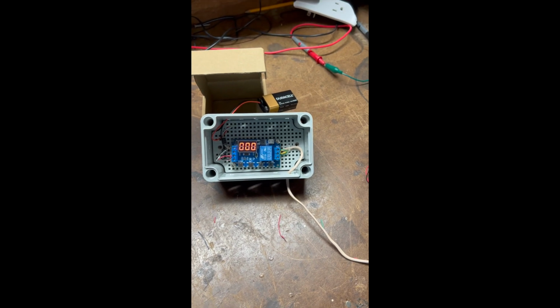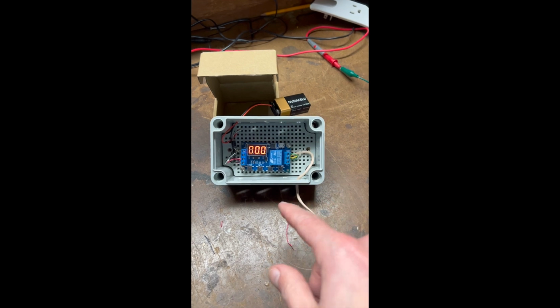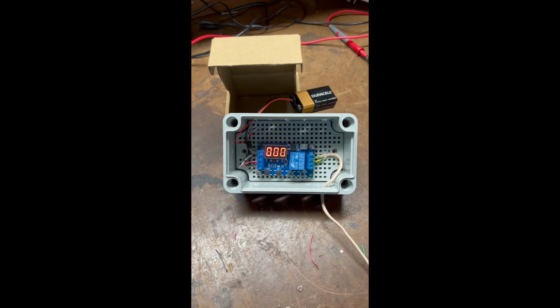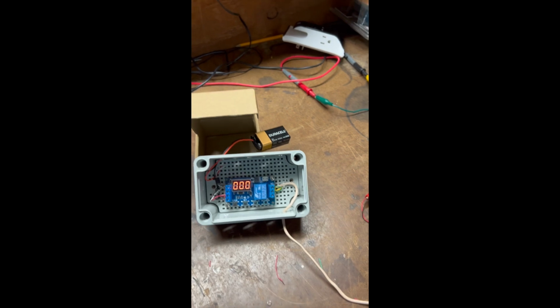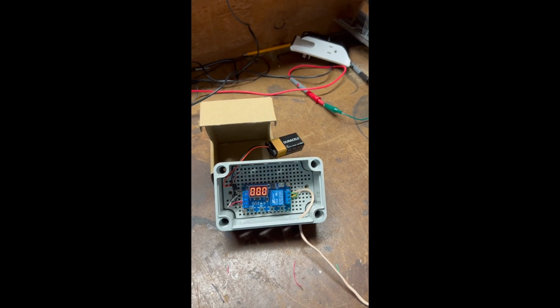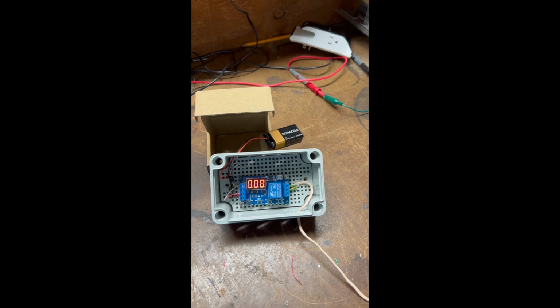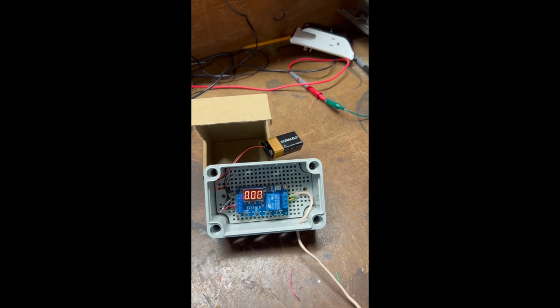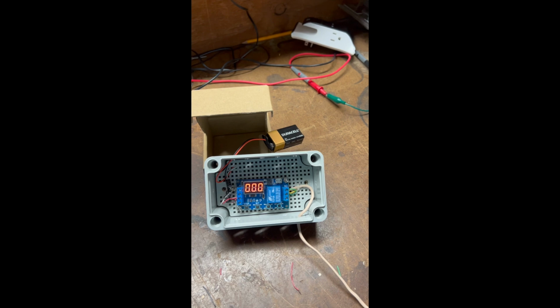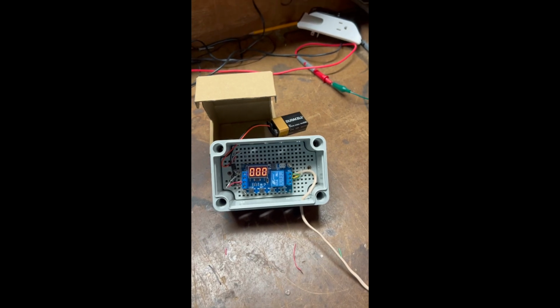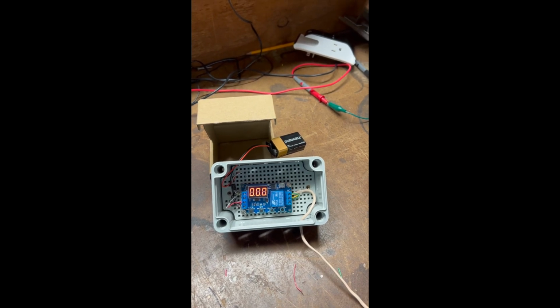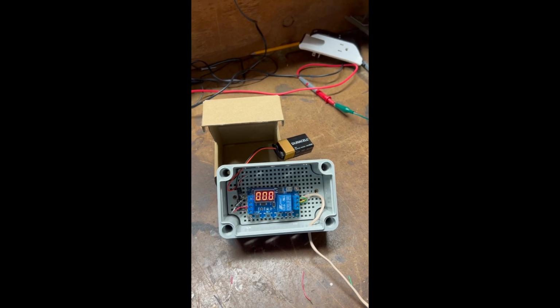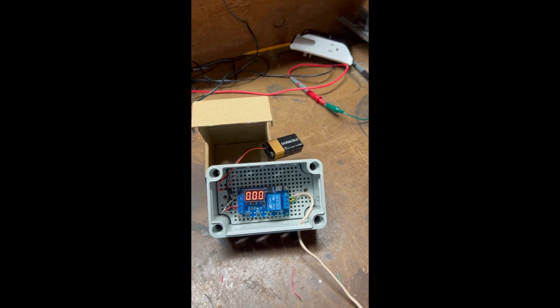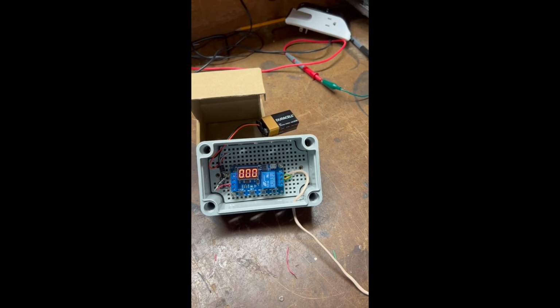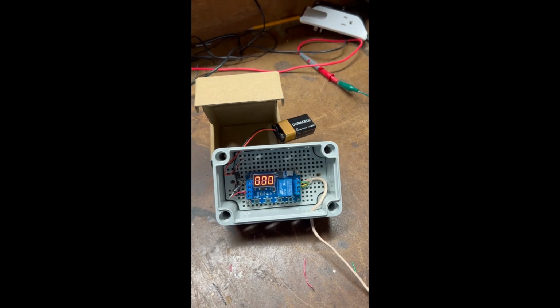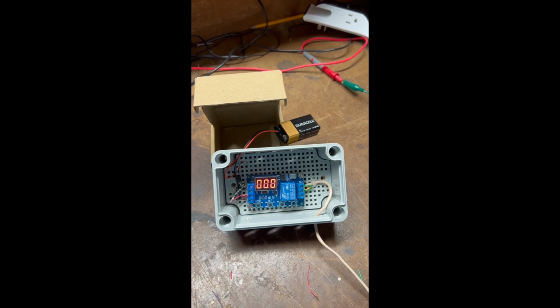We talked about originally how the way that it was wired before was on the normally closed side, and that was essentially a fail-safe. So if the circuit ever lost power, then the contacts would close and there would be an alarm condition. So you can actually argue that a couple different ways. One is there are instances where relays get welded into a closed position. Usually that's in high current scenarios, not something I would expect to happen here, but it's one possibility.